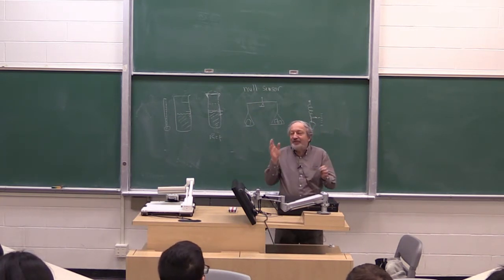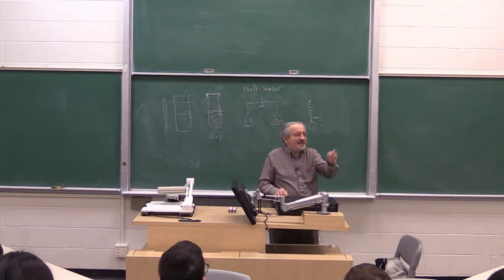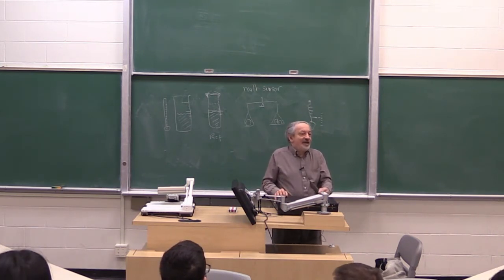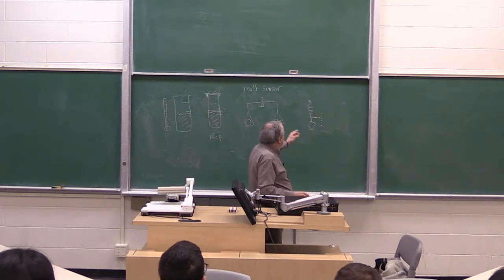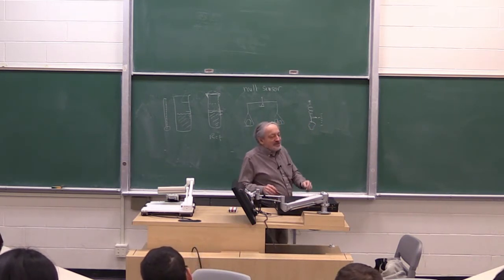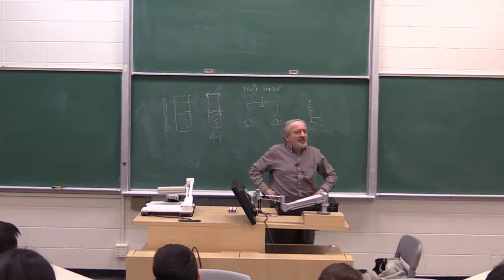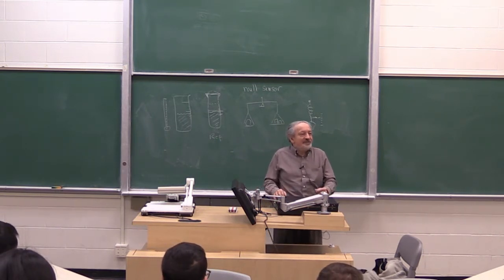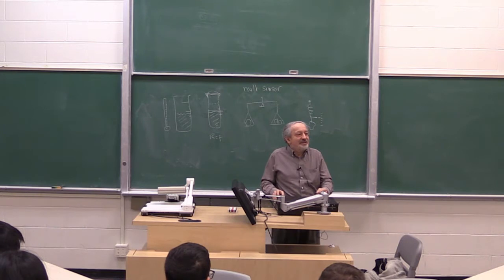But there's still one factor nobody mentioned. Gravity. And why is that a bigger factor? Because the linearity of the spring, the change of the spring constant with temperature, are usually at the ppm level. But gravity is a bigger factor, depending on altitude, because gravity depends on altitude.